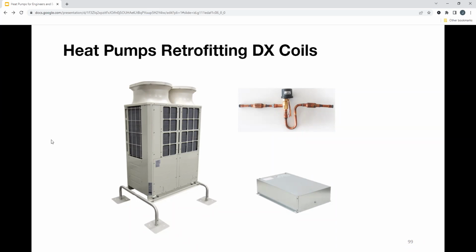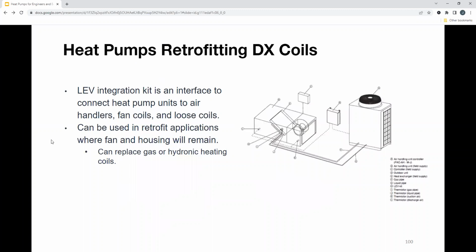And this right here, what I'm about to mention, is a great solution for retrofitting these air handling units, DOAS units, which is using these heat pumps and retrofitting DX coils. If you have a new construction project, you're also able to size a coil accordingly and use these heat pumps to provide cooling and heating. So what is it? It's an interface that connects our heat pump units to air handling units, fan coil units, or even loose coils and downstream ductwork. Anything you can put a DX coil in, we could probably retrofit using our heat pumps. So you can keep the fan and the housing the same. We just take out whatever that existing coil would be. Replacing gas and hydronic heating coils is primarily what we've been seeing in the field recently.